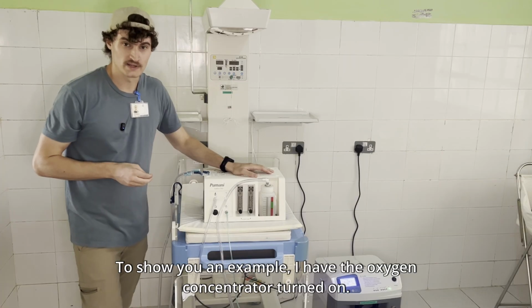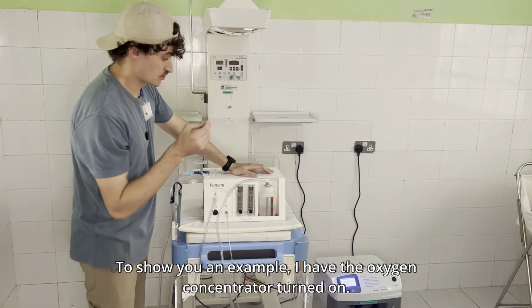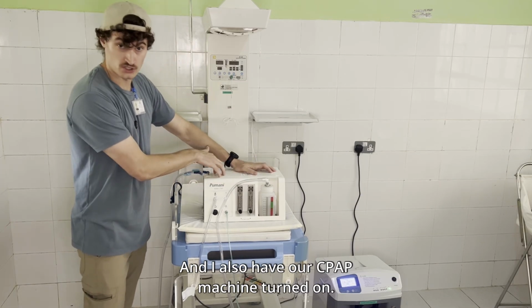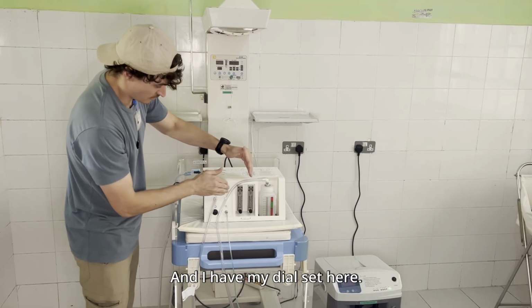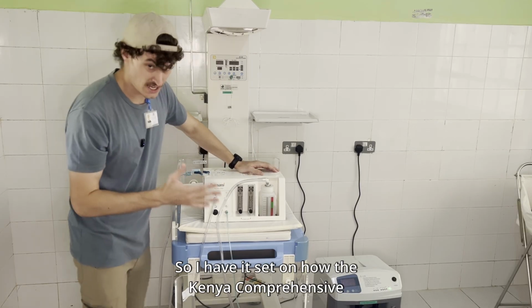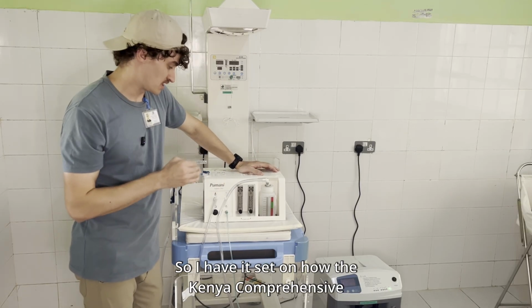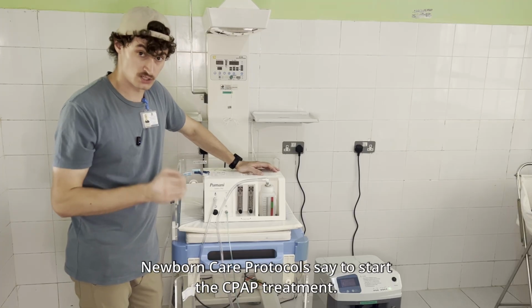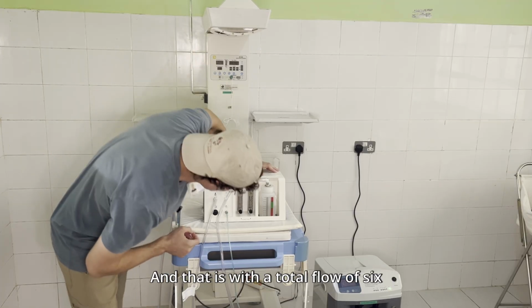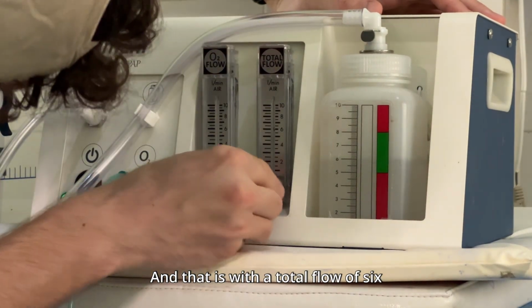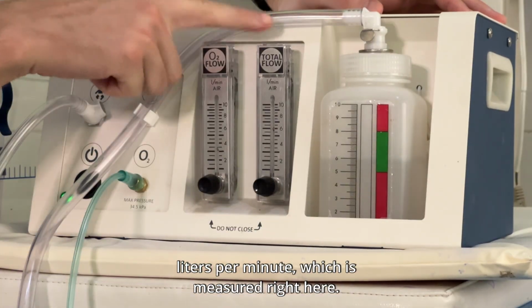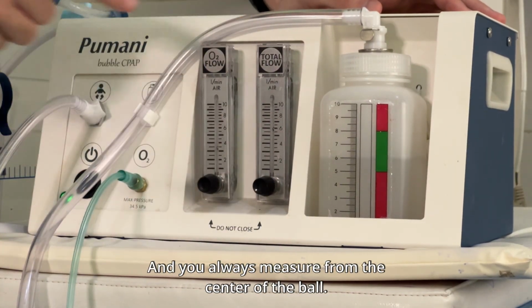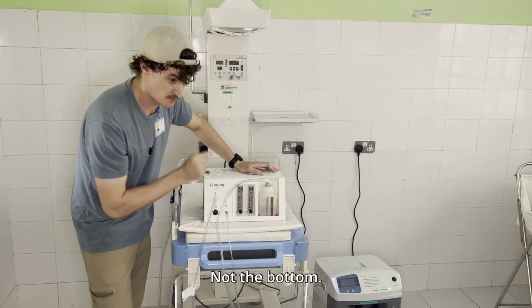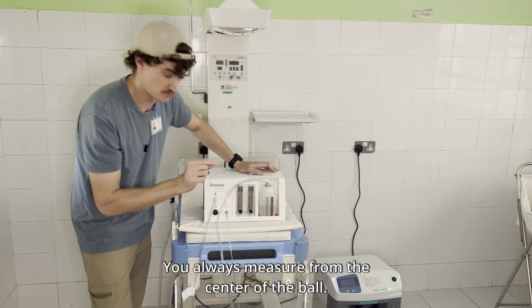All right, guys, to show you an example, I have the oxygen concentrator turned on, and I also have our CPAP machine turned on, and I have my dials set here. I have it set on how the Kenya Comprehensive Newborn Care Protocols say to start the CPAP treatment, and that is with a total flow of 6 liters per minute, which is measured right here, and you always measure from the center of the ball. Not the bottom, not the top, you always measure from the center of the ball.